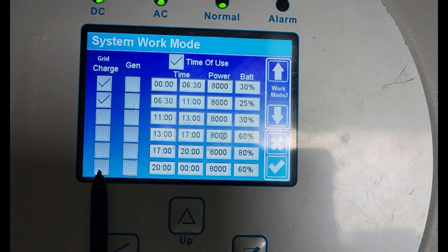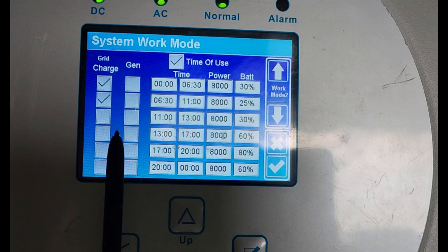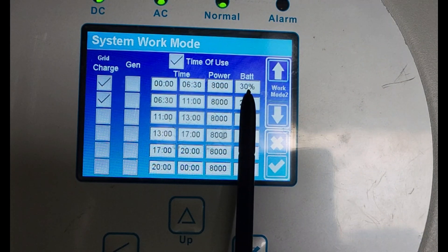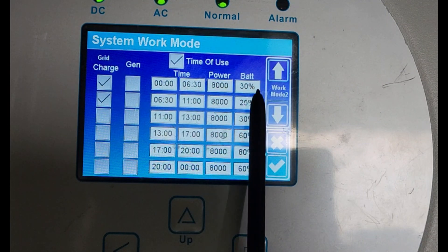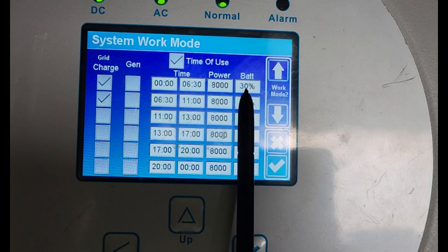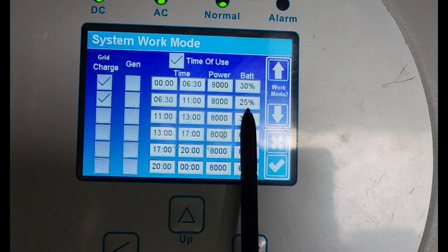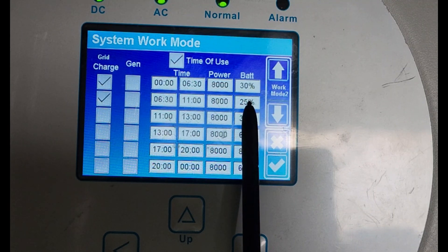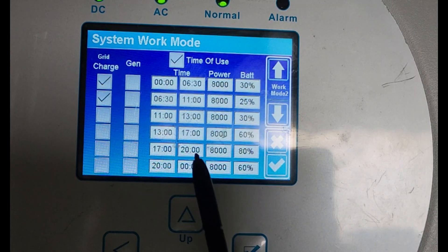Grid charge you can use — some people leave it off, I want to switch it on, but I expect never to use it. This will only really be if there was load shedding and it drops below 30% because there's load shedding — nothing can charge it, plus it's middle of the night, there's no sun or it's rainy. Then it'll drop below 30%. I've put my cutoff at 15% and my warning at 20%. So this is pushing it really close because my battery isn't that large, but I do want to use it to the maximum. So in the morning the sun will charge it again — if it drops below that because there's no grid and there's no sun, and the grid does come on again, then it'll charge it up to 30 and 25. That's kind of a backup.